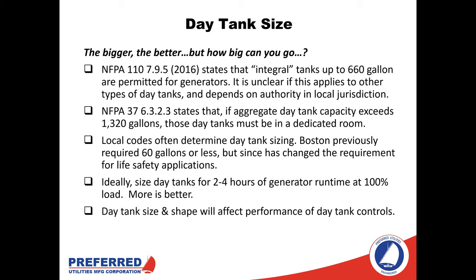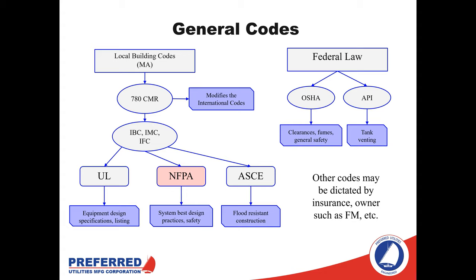More runtime is better, but we're limited by local codes on how large that can go. Here in Boston historically, we were requiring 60 gallons or less for the local tank. Thankfully that has changed — they're now allowing a tank sized for two to four hours if it's based on a life safety system, which allows the tank size to scale with the generator. Ultimately, no matter where you are in the country, the final say is always determined by the local fire inspector or local building codes.